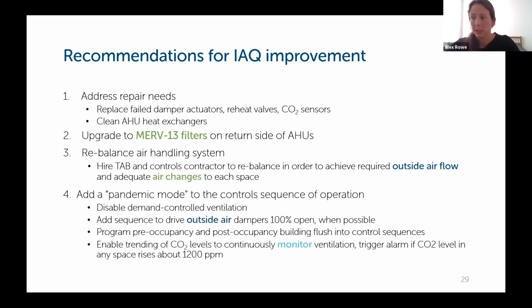And then add a pandemic mode to the control sequence of operation. So disable demand control ventilation for the duration of the pandemic in order to maximize airflow and outside air. And then add a sequence that drives outside air dampers 100% open if and when needed. Program pre-occupancy and post-occupancy building flushes into the control sequences in order to clean out the building air overnight. And then enable trending of CO2 levels to continuously monitor ventilation and potentially add an alarm if CO2 levels in any spaces rise above 1200 ppm.